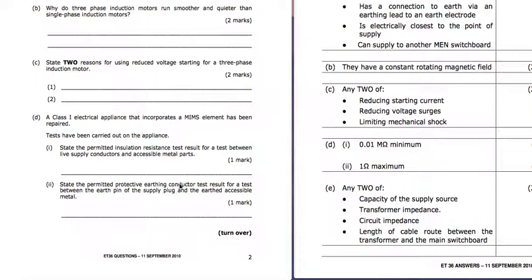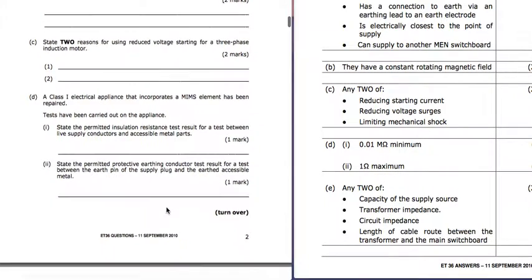The earth conductor test is still the same though. We're still looking for 1 ohm maximum. So the MIMS doesn't change that, it just changes the insulation resistance.